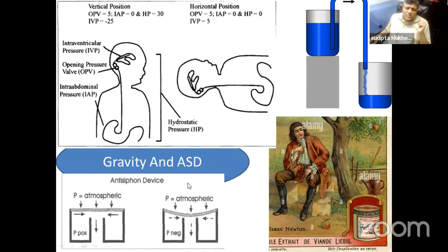This is the device, how it works. See, there is a thin membrane over the shunt device in the inlet or outlet. If atmospheric pressure is too high and pressure within the shunt is too negative, the thin membrane comes toward the valve and occludes the inlet or outlet at the same time. So that is the mechanism by which the anti-siphon device acts. See another example. This is a valve where the blue color on the left is the inlet, the blue color on the right side is the outlet, and there is a thin membrane on one side.